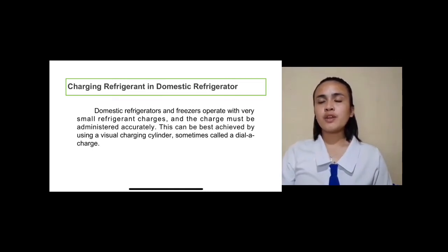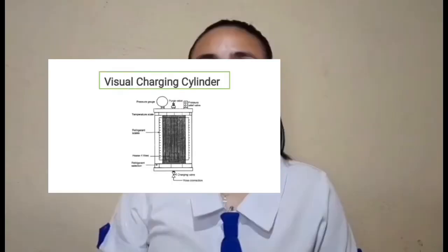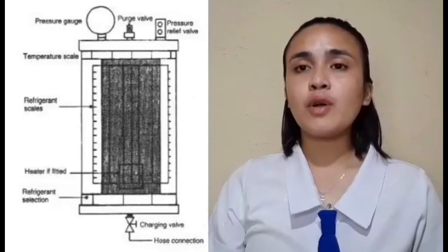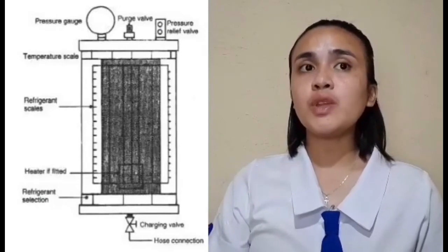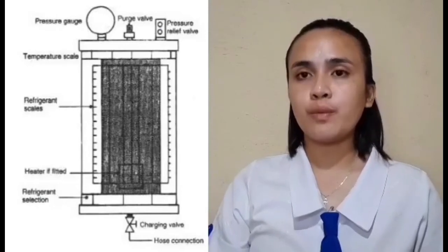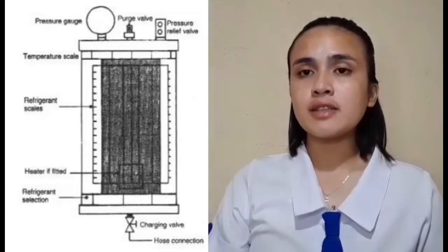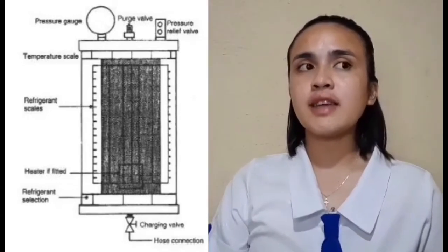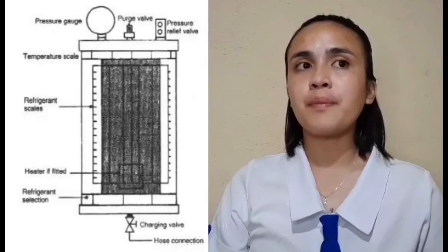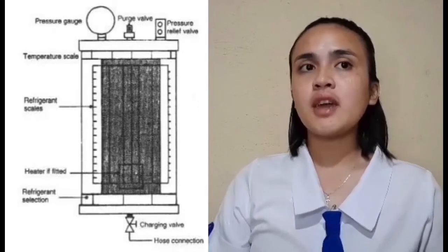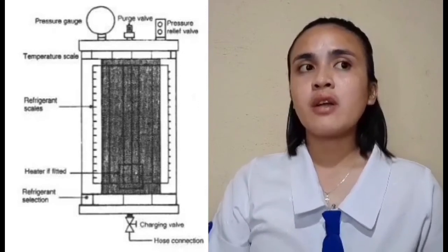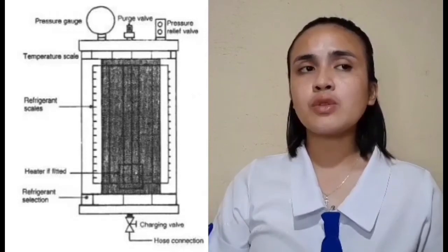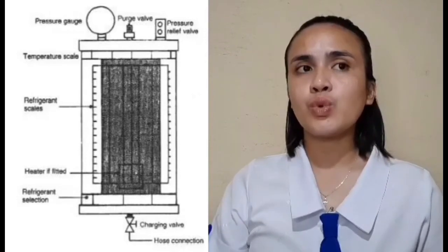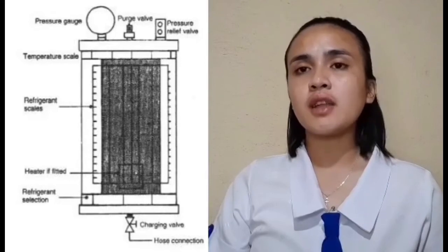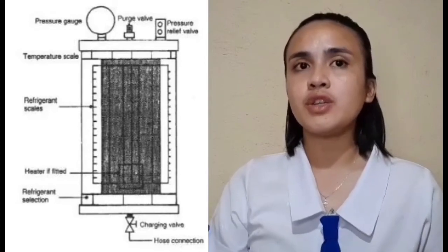So I will show you the visual charging cylinder. This is basically a small refrigerant cylinder with a liquid indicating sight glass or tube. In front of the sight glass and surrounding the cylinder and sight glass is a rotating screen upon which are graduated scales for the common refrigerants R12, R22, and R502. Above the refrigerant scales is a temperature range.